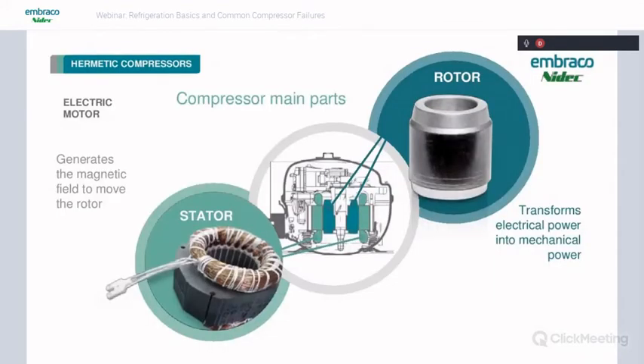So this is a better look at the motor inside the compressor. You can see the stationary part, the stator that holds the windings of the compressor. And inside that, you have the rotor, which has the crankshaft going through the center of it. So the stator generates the magnetic field to move the rotor, and the rotor transforms the electrical power into mechanical power through the crankshaft to the reciprocating assembly. And you can see how the stator is orientated in this motor here with the rotor inside of that. And there's an air gap in between that rotor and stator.